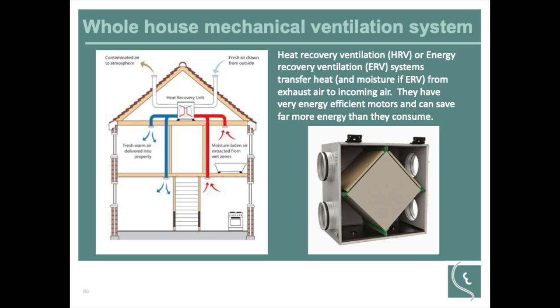This HRV or ERV fan is not a requirement. It's just optional. It's an option for whole house mechanical ventilation. Ventilation is required. Right. You don't have to use an HRV or ERV to do that. That's true. That's what I'm saying. Yeah, you can have the continuous, we've seen that before, the continuous running Panasonic fan just exhausting.